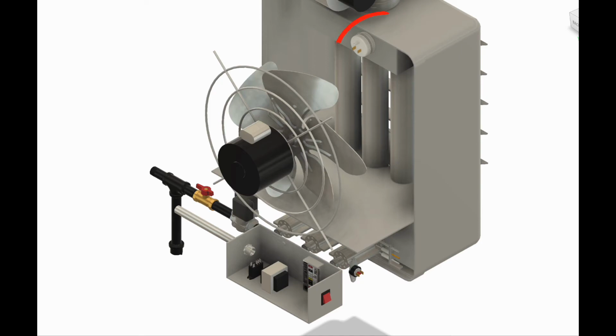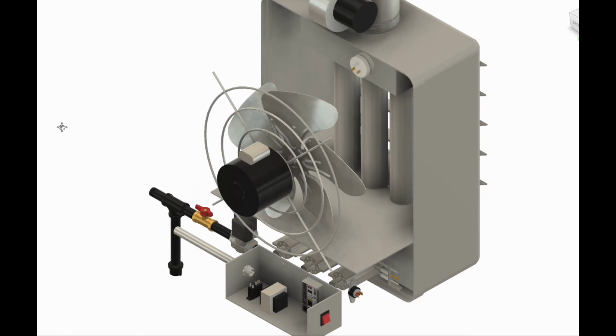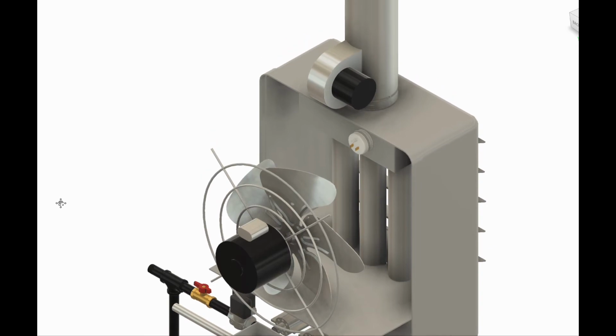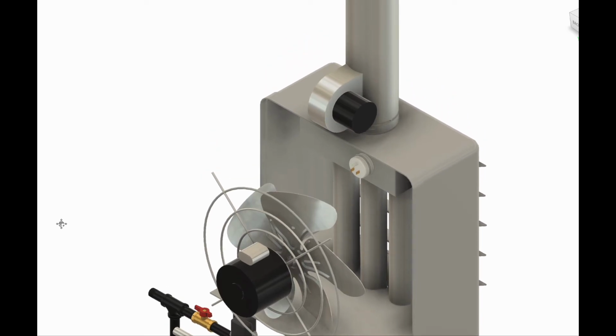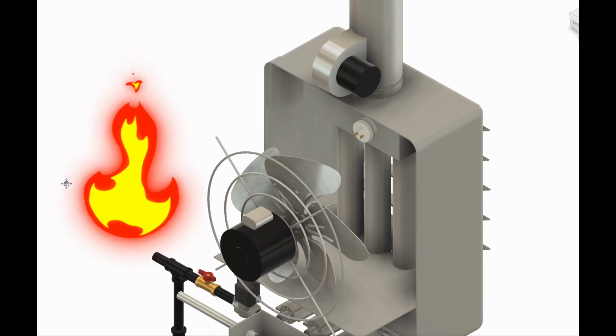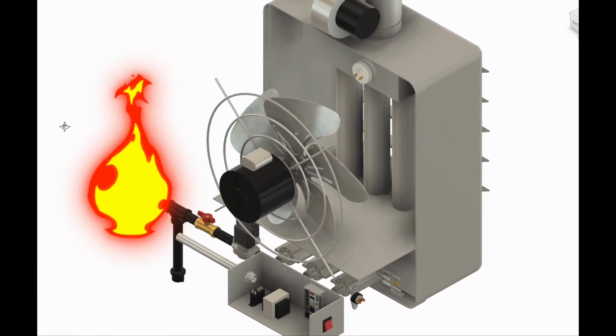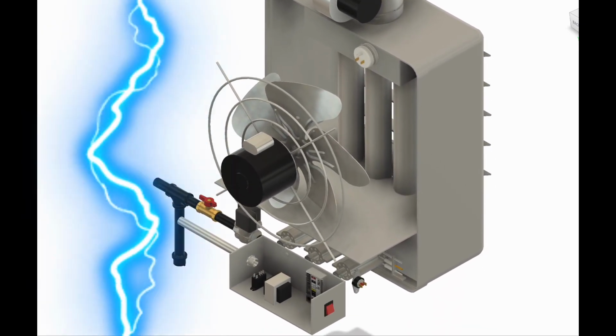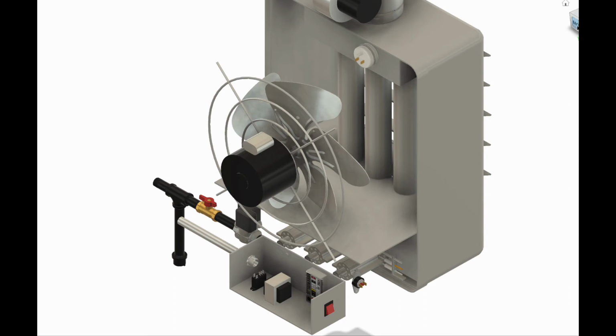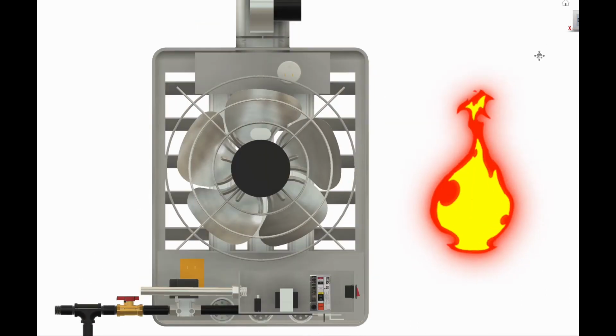There's the pressure switch or air proving switch. So when the draft inducer fan starts, that switch will close. That then tells the ignition control board that it's safe to open the pilot and light the pilot light. Once the pilot light induces a current down the flame sensing rod, then the main burner will light.